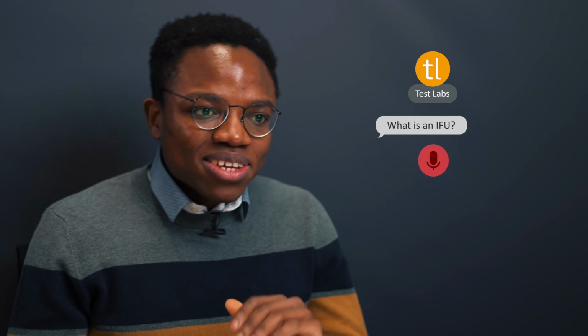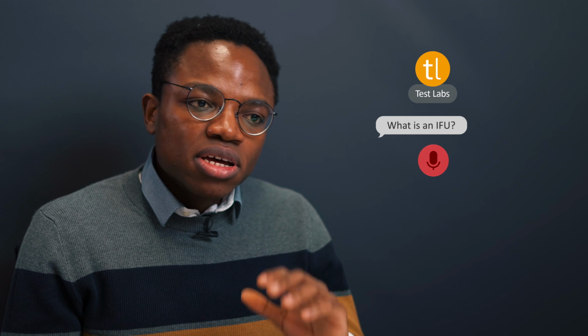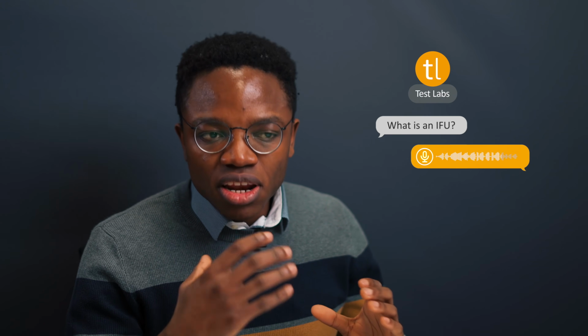I suppose for the next question, what is an IFU? Very nuanced topic. So in simple terms, once again, an IFU is an instruction for use manual. Think of it like a guidance documentation provided with just about every single medical device, and it details how to use that medical device, how to reprocess that medical device, any indications and contraindications you might need to know about, the intended population, and most importantly, who this should never be used on under any circumstance. Following a proper IFU is a very, very important thing for your medical device's life cycle to last as long as possible.